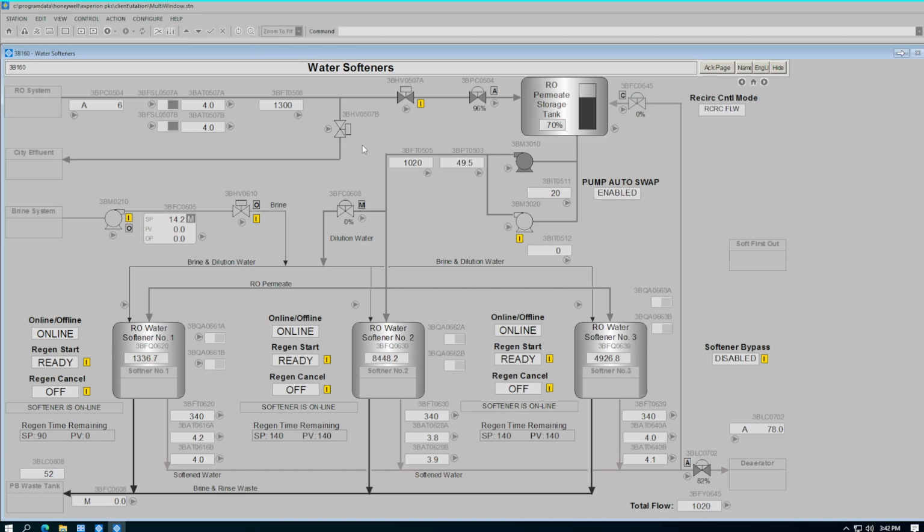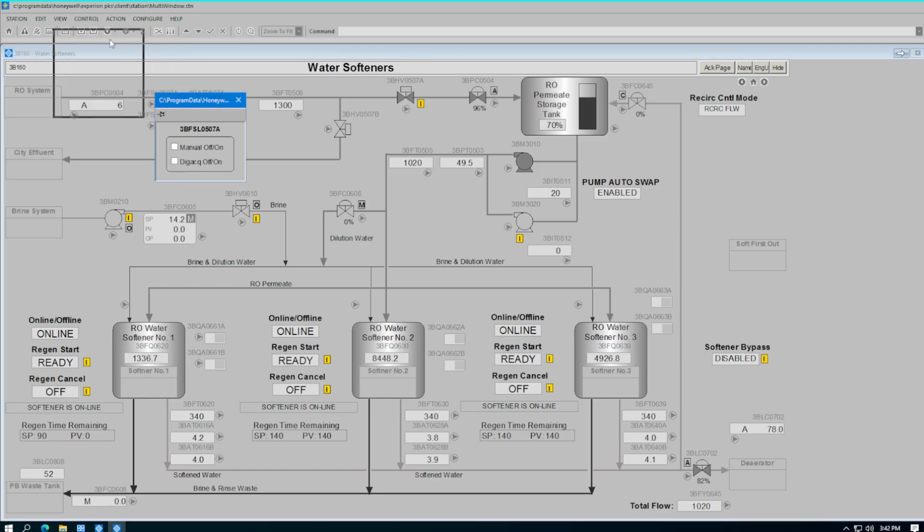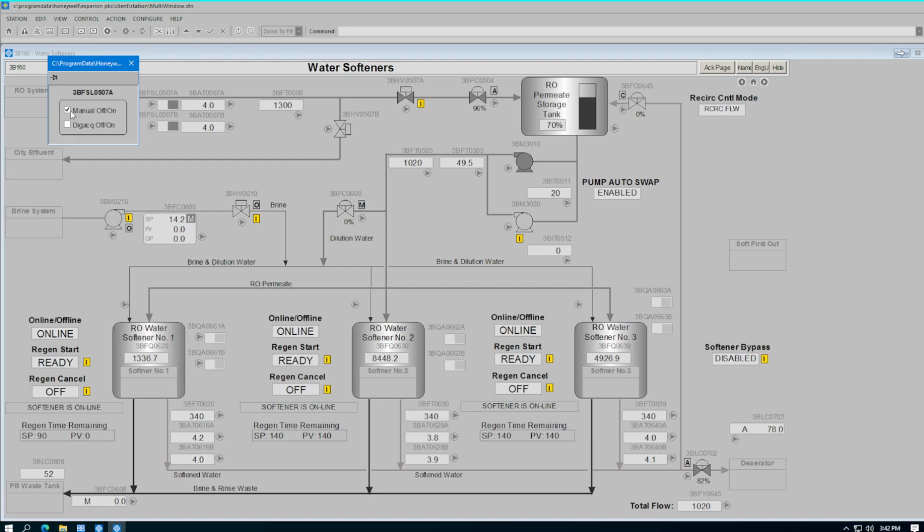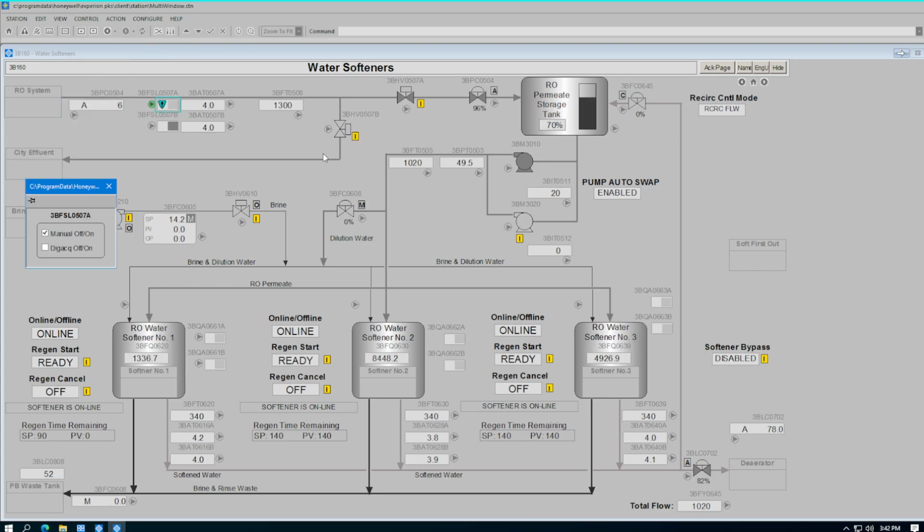We will now demonstrate the permeate divert. This is what happens when we lose flow to one of our conductivity probes. As you can see, valve B opens. 10 seconds after a confirmed open, valve A will close, preventing flow to the permeate tank.